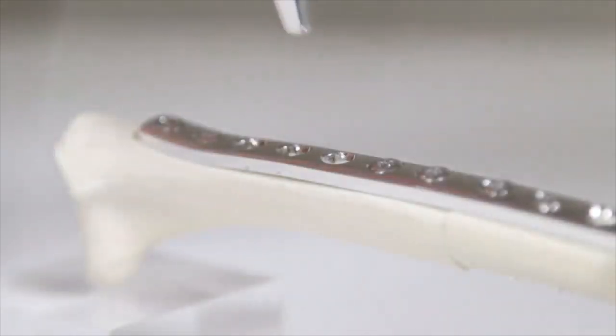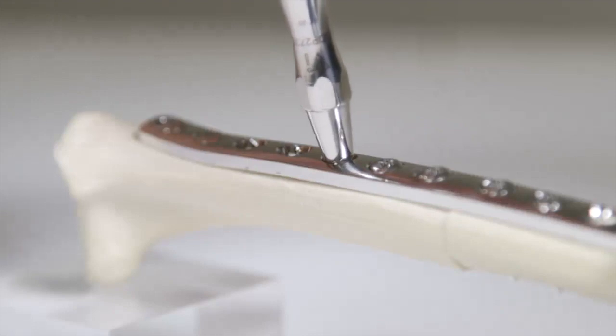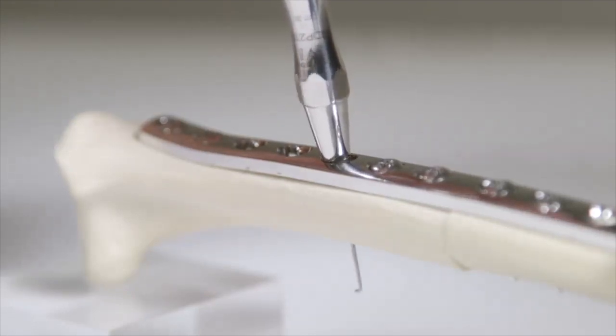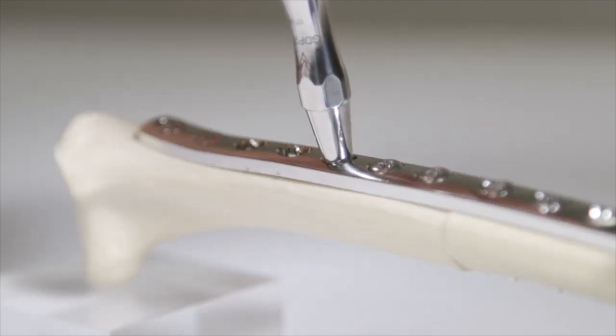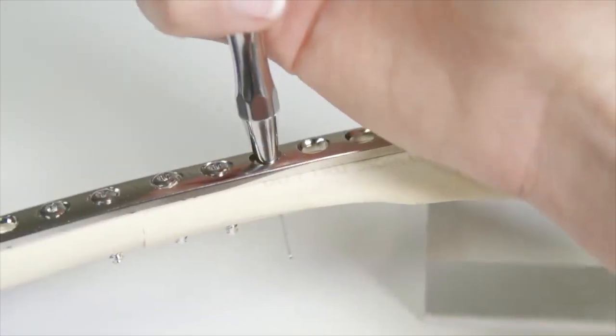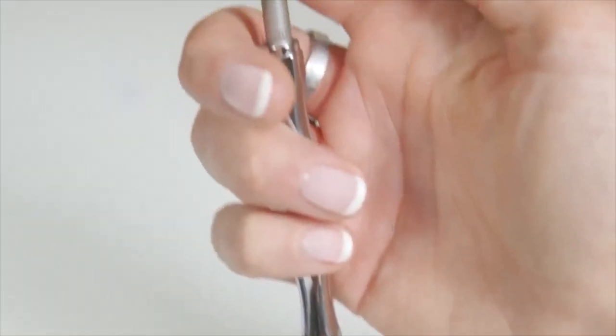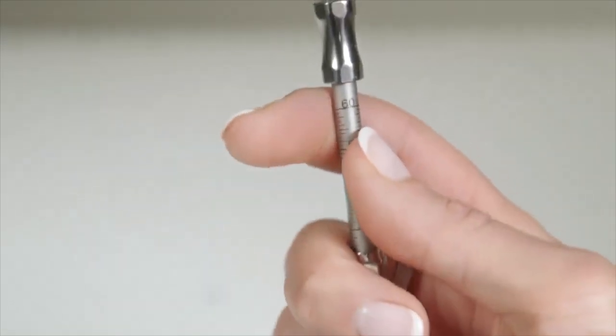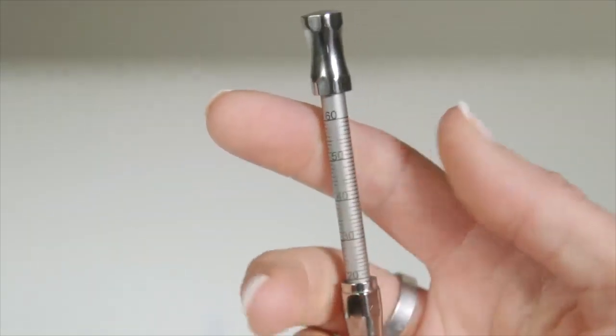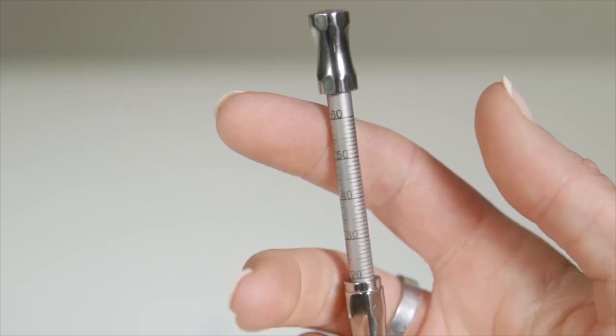The tip of the device may either be placed into the plate hole or positioned directly onto the bone. The probe is extended into the pilot hole. The tip of the probe is then retracted to catch on the edge of the hole at the far cortex. The depth of the hole is then read from the scale on the device. The reading on the scale gives the actual depth of the pilot hole, cortex to cortex.